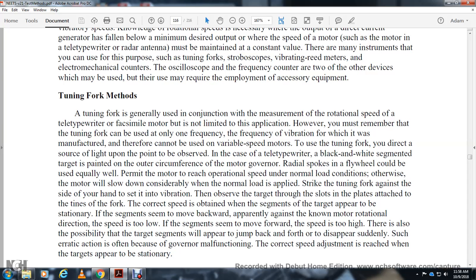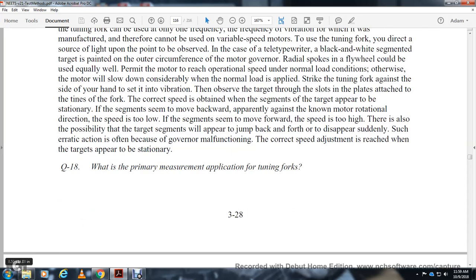Apply the standard tuning fork, held by the side of the hand, and set it into vibration with the slots in the plate attached to the tines of the fork. The correct speed is obtained when the segments of the target appear stationary. If the segments appear to move backward, the motor speed is low, and if they move forward, the speed is too high. It is also possible the target segments will appear to jump back and forth or disappear suddenly. This erratic action often indicates governor malfunction. The correct speed adjustment is reached when the target appears stationary.